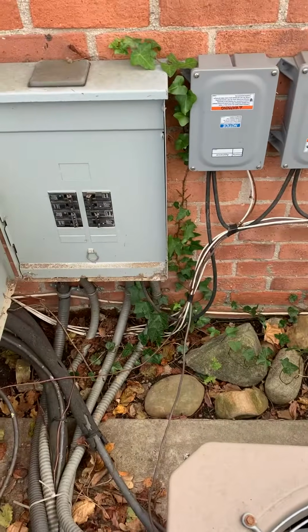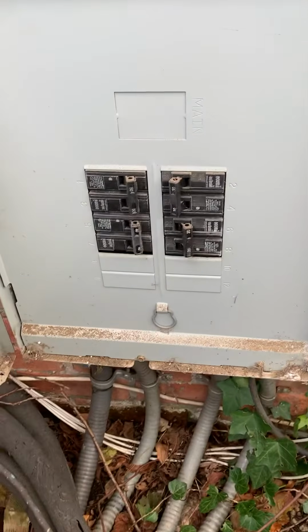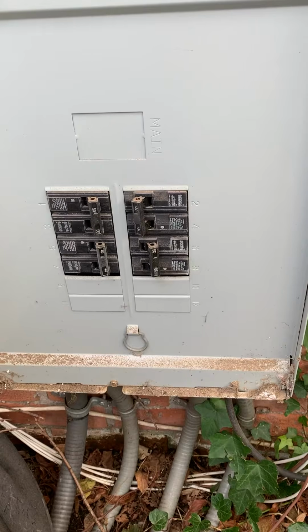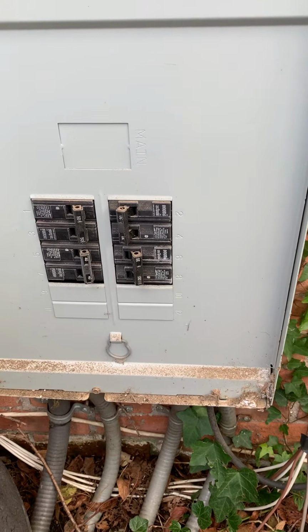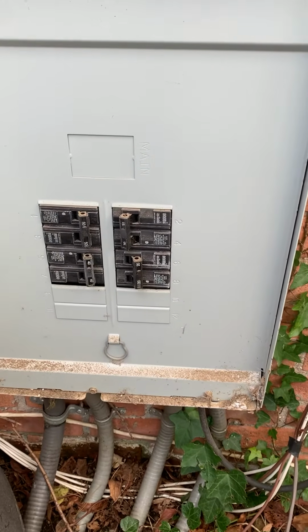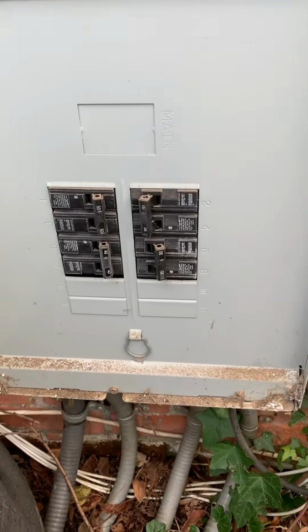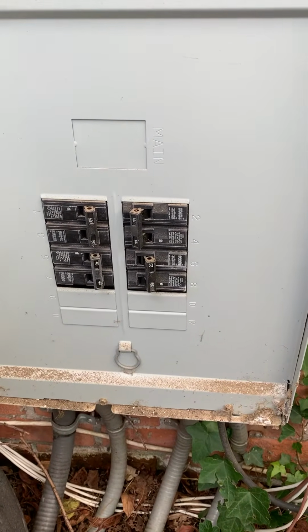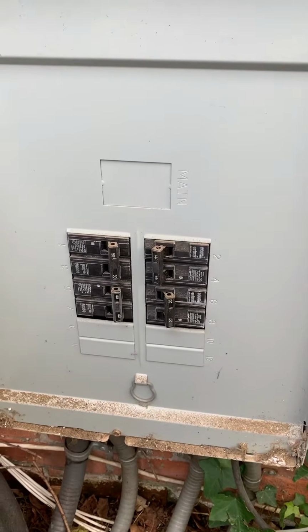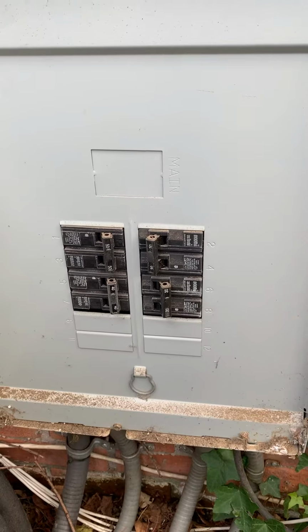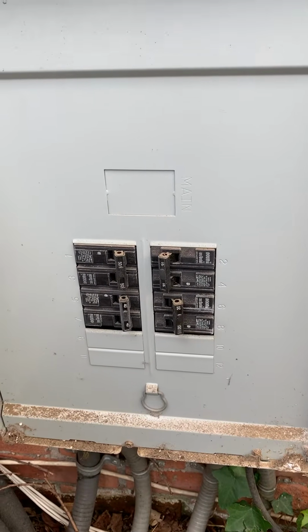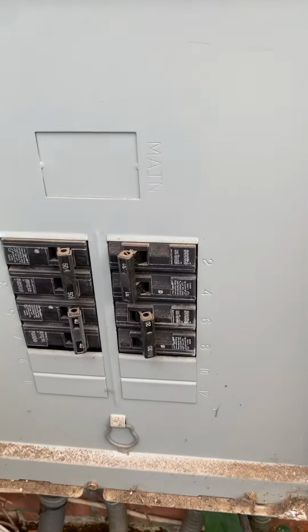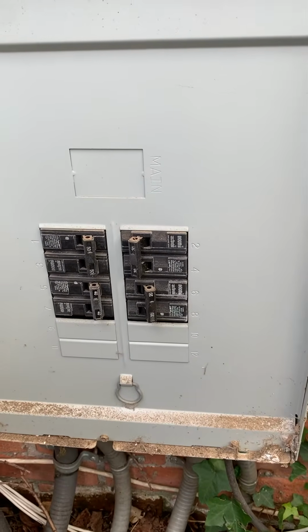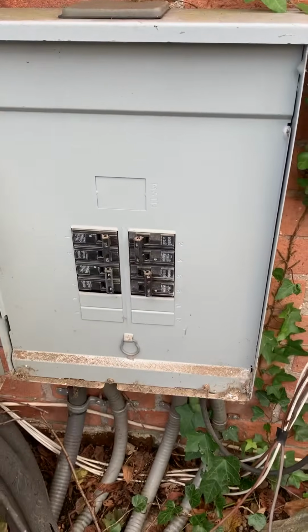All right, guys, so just want to bring this out real quick. I go to the circuit breaker box. It's got 4 circuits, 3 of them on, 1's off. I had to find out which unit this was, so I turned on all the thermostats on the house, except for the one downstairs. This one went on. This one went on. That one went on. This one did not. The one that I'm having a problem with is most likely this one here, and that one's off. So somebody was here, knew it was a problem, shut the breaker down, and didn't tell the homeowner, or the homeowner didn't tell me. So I think they didn't know, maybe it was the contactor. We'll dive into it a little bit more. I just wanted to show you this, what some people do.